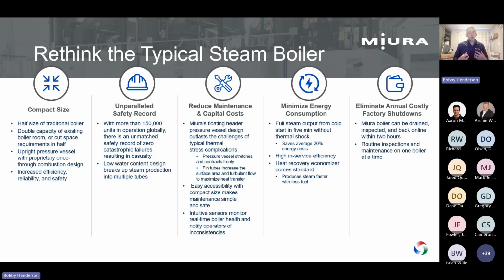So when Miura took to designing this boiler many years ago, they rethought everything about the typical boiler. The Miura design is about half the size of a traditional boiler, and they've built over 150,000 of these units worldwide. It's a Japanese company, and over the past 40 years they've had zero casualties from this boiler design, which we certainly cannot say with the traditional fire tube design.